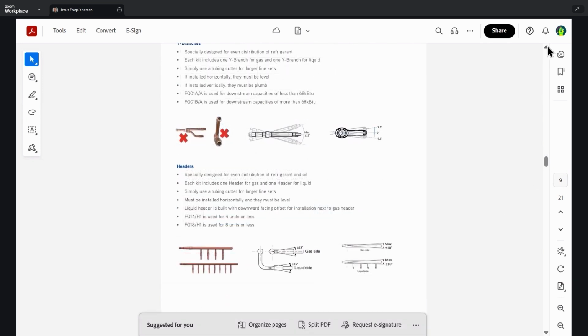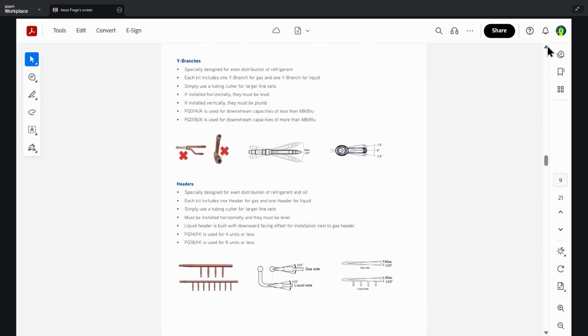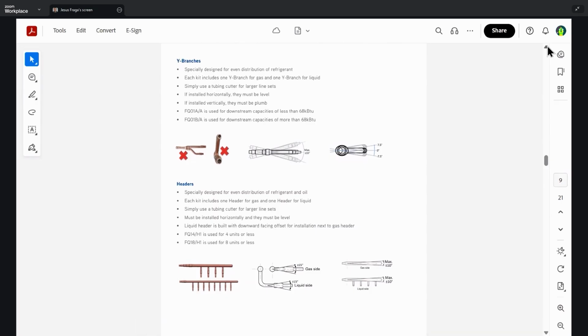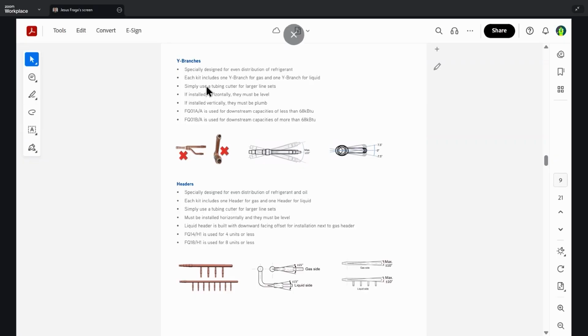Moving on. Y branch and header installation. This is very important when it comes to installation to avoid things like compressor failures, inadequate cooling, and increased energy consumption. The installations of the Y branches and the headers are crucial. As we know, they're specifically designed for even distribution of refrigerant. Each kit includes one Y branch for gas and one Y branch for liquid.